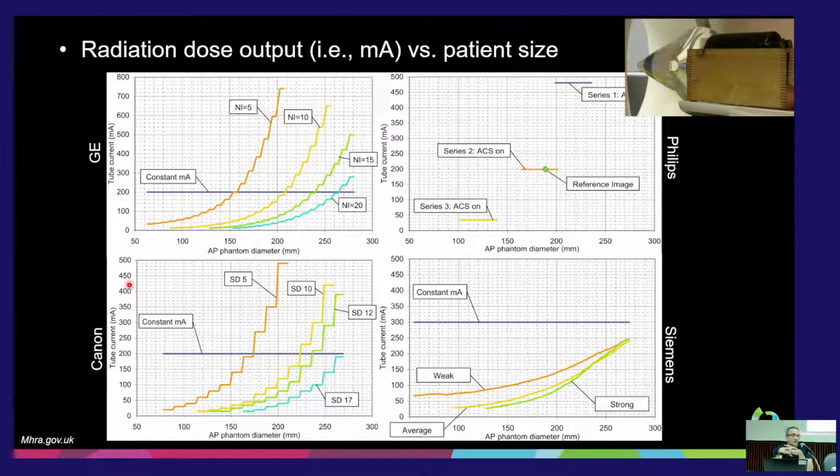Dr. Cannell and I were talking about this yesterday. One of the questions we were faced with was that we were looking at a high-res chest protocol on one scanner and the other, and the CTDIvol value was much lower on one of the vendors. As we looked through it, we came to the conclusion that it's most likely the choice of the noise index on the one scanner versus the quality reference mAs on the other, and how one doesn't rise as fast whereas the other rises faster. So reducing the noise index on that one scanner would probably put it a little closer in line with what you see on the Siemens scanner.